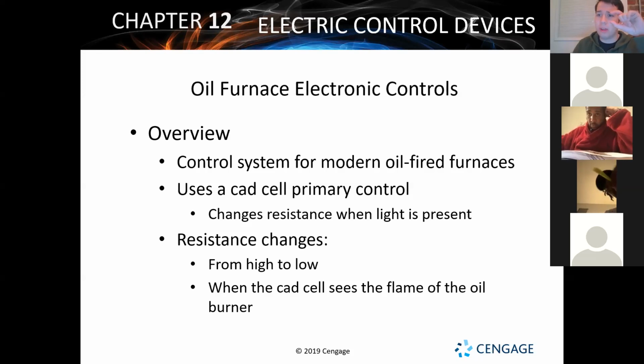If you cover that up, you're going to see that resistance go way up. But as soon as you take your thumb off and you shine a light directly into that CAD cell, you'll see the resistance drop way down. And that's how it works. It literally just watches to make sure that there's light. For an oil furnace, this is how it says, yeah, I know we've got a flame in the system, because there's light, unless someone's down in the oil furnace heat exchanger with a flashlight trying to trick it or something like that. So that light is proof of a flame, and then that's a safety.